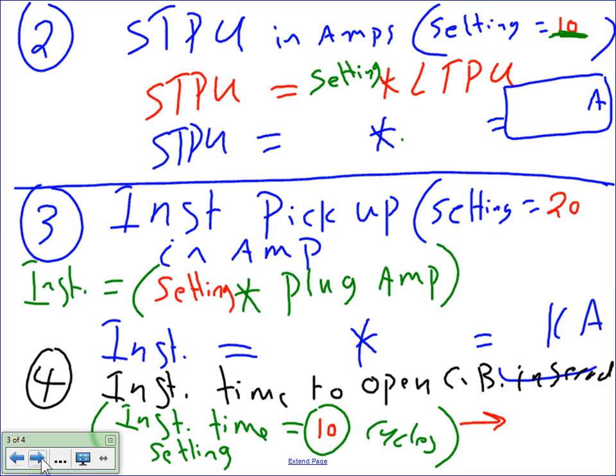The formula is short time pickup equals the setting multiplied by the long time pickup. What's the setting? The 10. What's the pickup? 1400, right? Long time pickup in amps is 1400. If you do your math on this, you're going to end up with 14K, so 14,000 amps. That's the short circuit or ground fault at which the circuit breaker is going to trip. Short time pickup is mostly ground fault and low level short circuit.